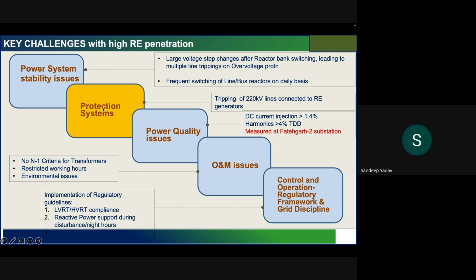Then there are issues which are related with protection systems. We just talked about a few slides ago. There are power quality issues, because these devices are switched in nature and they produce considerably large amount of harmonics as compared to the conventional sources. So conventional sources, given the uniform distribution of the stator winding across the periphery of the stator, we have very little harmonics in the system, or close to zero harmonics in the synchronous machines.